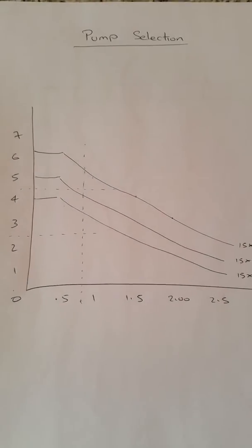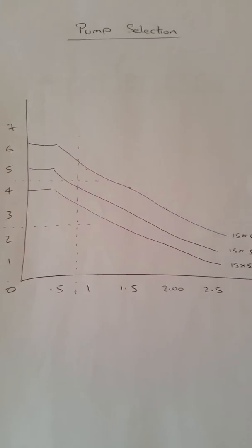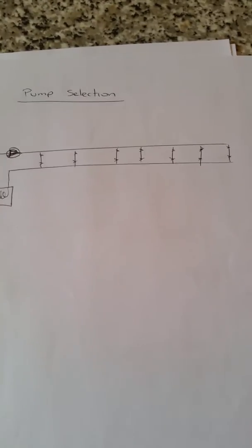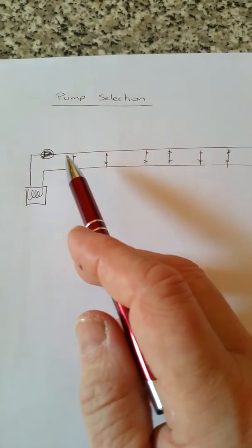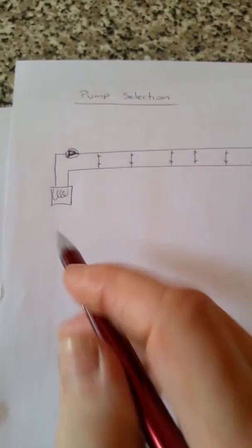So if you look at the pump graphs, we need to know what they mean, and why we need to select from the pump chart. Further back in the design process, before we get to the stage of selecting the pump, we calculate the mass flow rate for the system, and we also calculate the resistance to flow of the index circuit, and also we take into account the resistance of the heat exchanger.